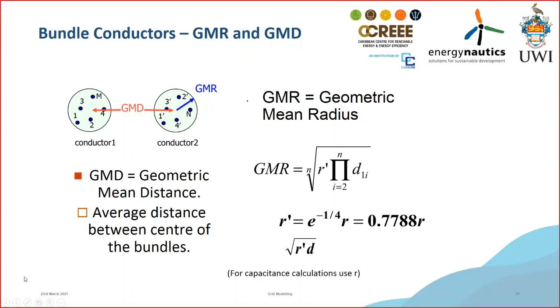That is what is going to give me the actual impedance of the line as seen by my power system network. So you need to get this data done properly, or else you're going to get wrong values in your analysis. One has to be very careful in how I do this. You cannot neglect how your conductors are laid in the ground as well as overhead, because each formation you use is going to cause a variation of the impedance of the line.